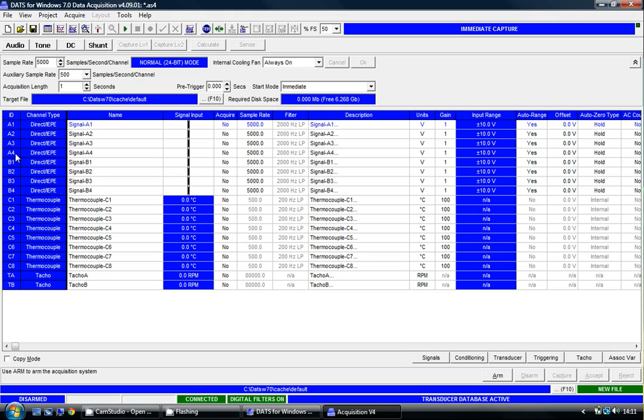Module A, Module B, and Module C. Module A is a four-channel BNC analog input. Module B is a four-channel BNC analog input. Module C is an eight-channel thermocouple input.